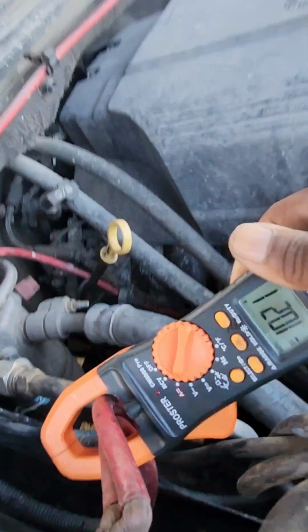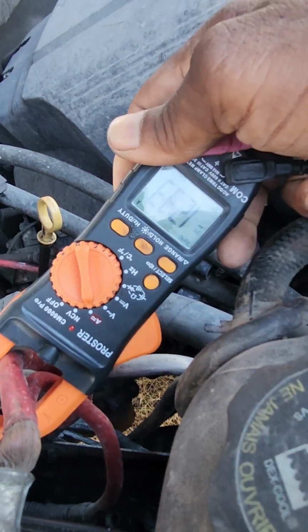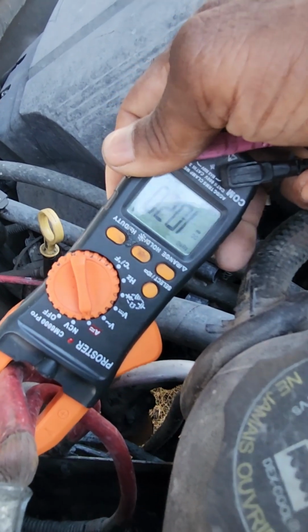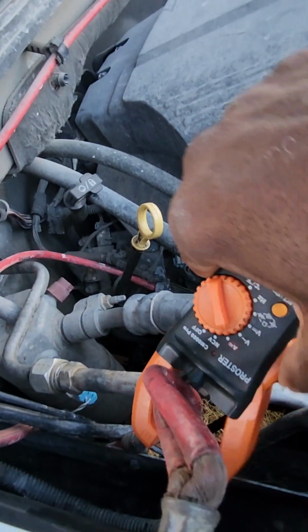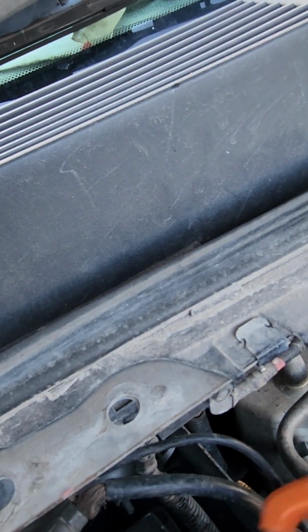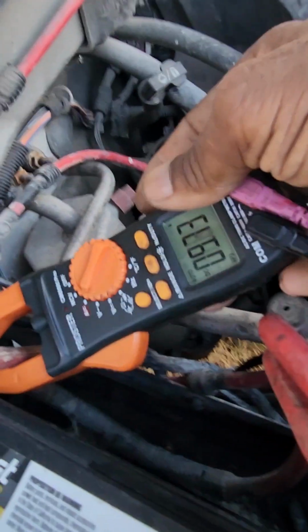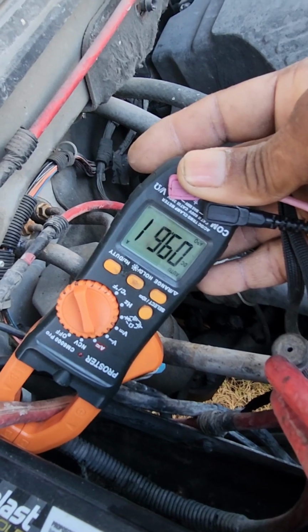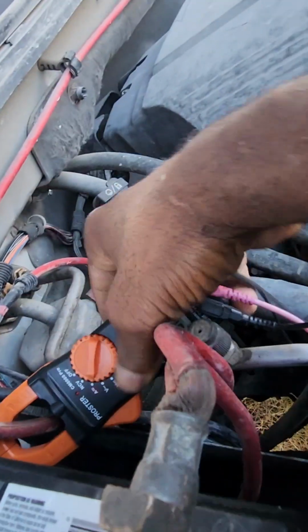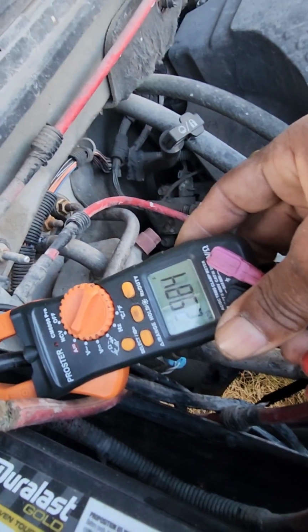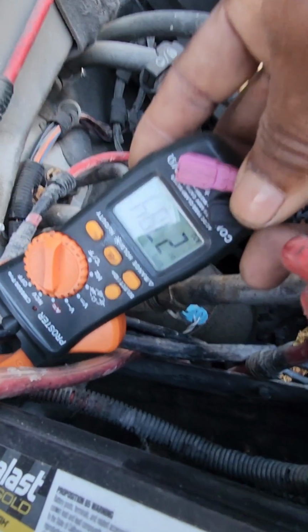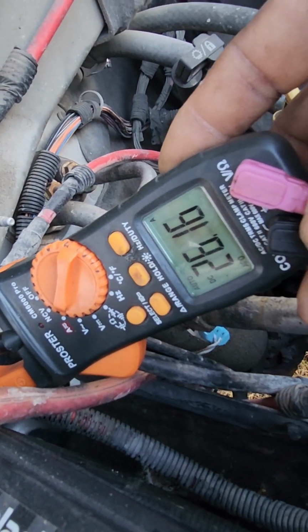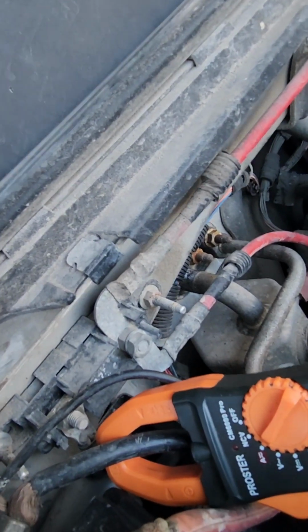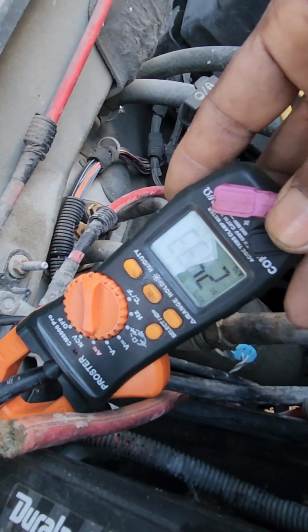See 11.8, 12.8, 9.8. Now if you were to go in and cut on the air conditioner, it would go up. And the reason it's not charging much is because the battery is fully charged. If the battery was dead, it would be charging a whole lot more amps. And that one's not connected. This one is. And that one says, okay, it just went up. Now it's charging 28 amps.